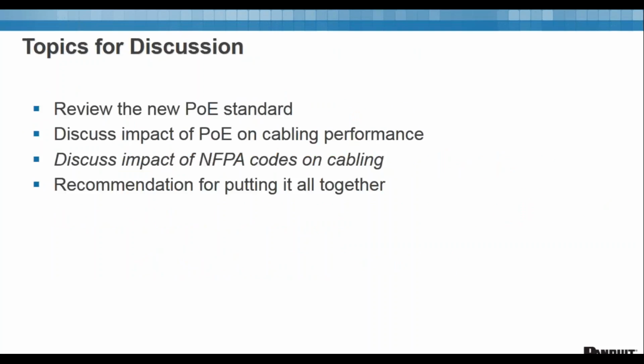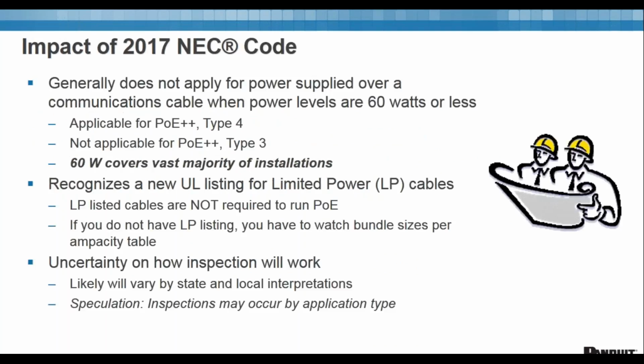All right, now we're going to talk about the impact of the new National Electric Code on cable. So, the impact of the 2017 code. It generally does not apply for power supplied over a communications cable when power levels are 60 watts or less. And what does it mean? If you recall, there are 2 types of PoE we are mentioning that are coming. There's Type 3 and Type 4. It is applicable for Type 4. It is not applicable for Type 3.